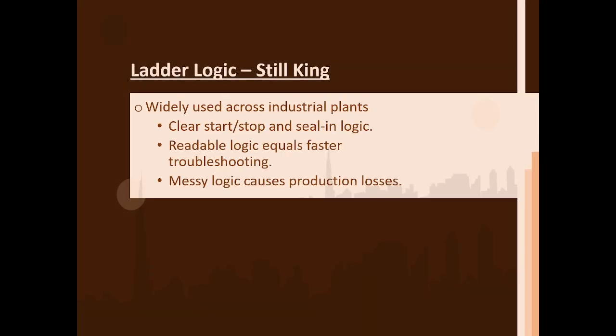Like I said, ladder logic is still key. Ladder logic is a programming language that visually resembles electrical relay circuits. It is widely used because it is easy to read, easy to troubleshoot, and easy for maintenance teams to understand. Clear ladder logic allows engineers to quickly find faults. Messy logic slows everyone down and causes production losses. So safety and protection logic are built on this clarity. And this brings us to what we call interlocks and trips.